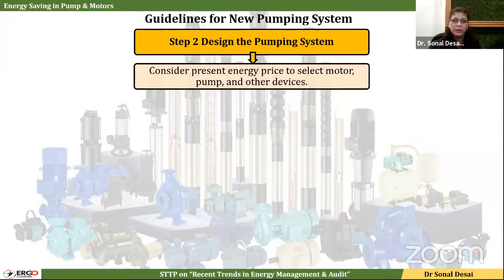When we are designing a pumping system, consider present pricing to select the motor. If your pumping system is older than 15 years, you have to blindly replace it, because 15 years back, the energy cost was something different. At that time, pump cost was a priority. Today, running cost is a priority. So if you are in the engineering field, engineering industry, and you have a pump which is older than 15, 20 years, rather than running that old machine, you should replace it. Always remember that old is not gold when we talk of energy efficiency. Old is always consuming more in the energy efficiency field.